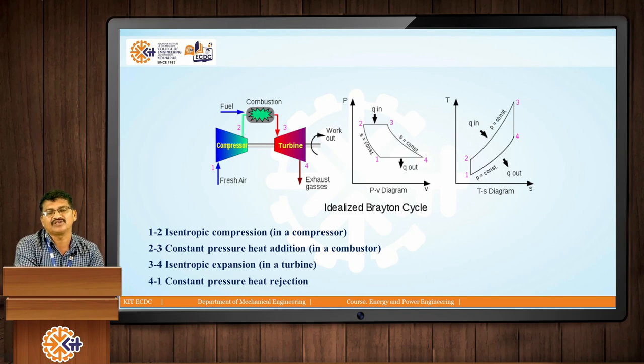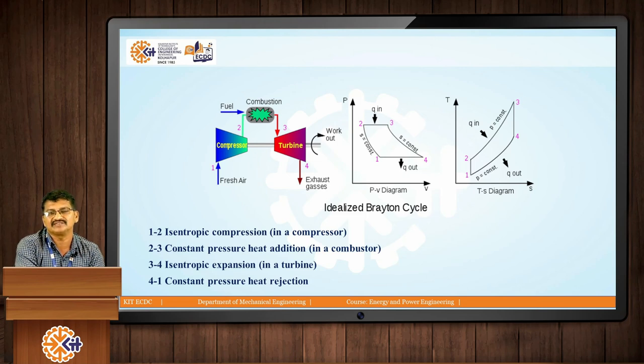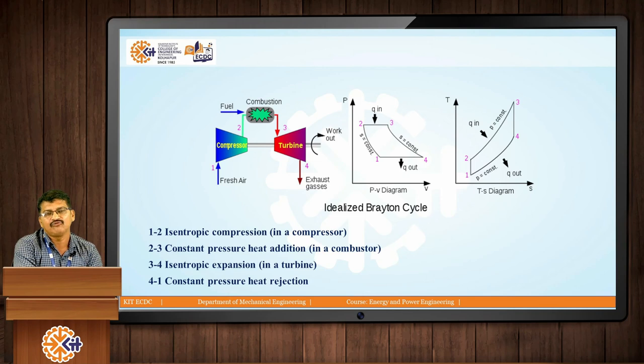From the combustion chamber, the exhaust gases go to the environment. After receiving heat, the argon or working gas enters the turbine and expands, generating electricity via the generator. This gas then goes through a closed loop back into a heat exchanger, where heat is rejected using circulating cold water or cooling fluid. The heat is rejected and the gas re-enters the compressor. The same gas is continuously circulated in the closed cycle gas turbine power plant.